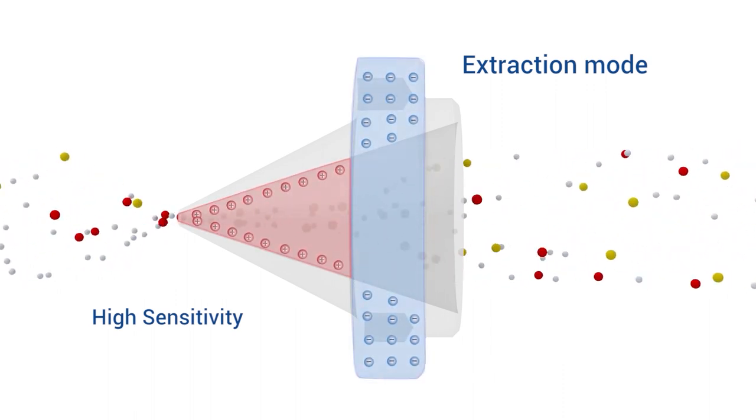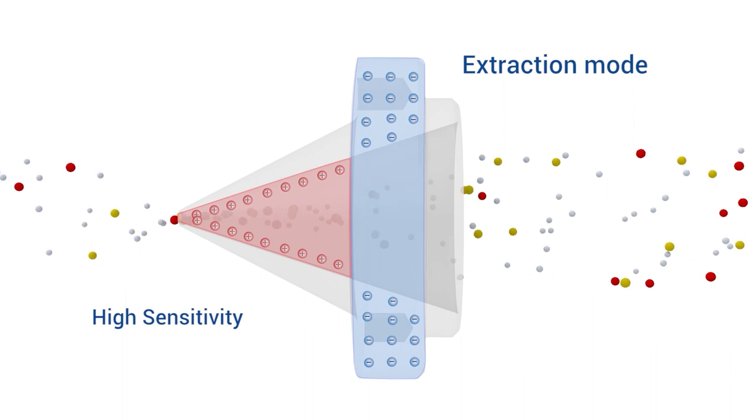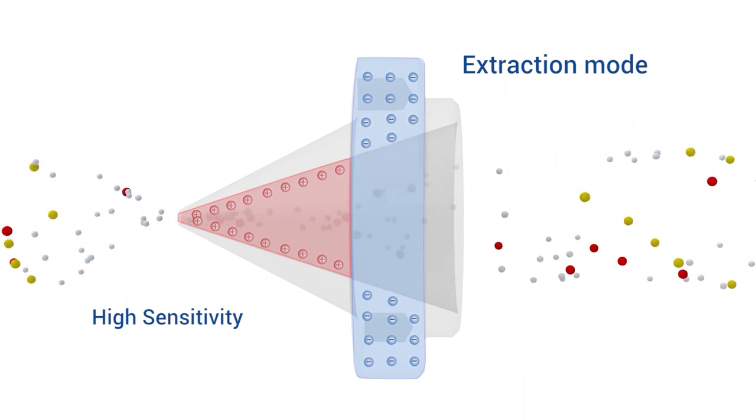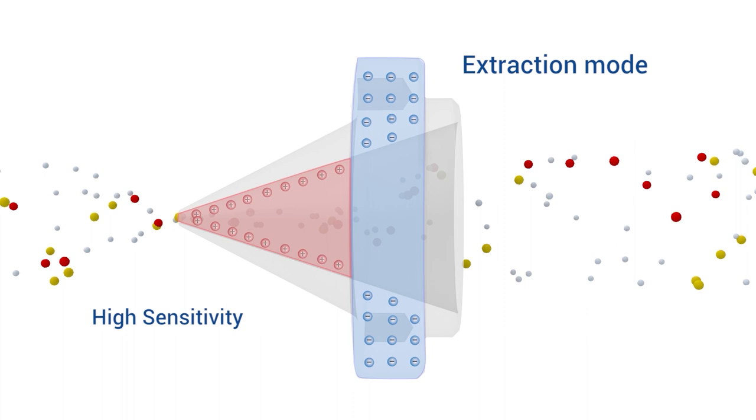Extraction and cold plasma modes help eliminate space charge effects by accelerating positively charged ions through the interface with minimal expansion, then focusing them before they enter the ion optics. This produces the most tightly defined ion beam in the industry, dramatically improving sensitivity.